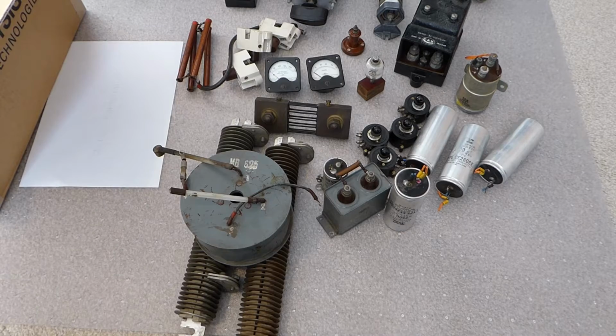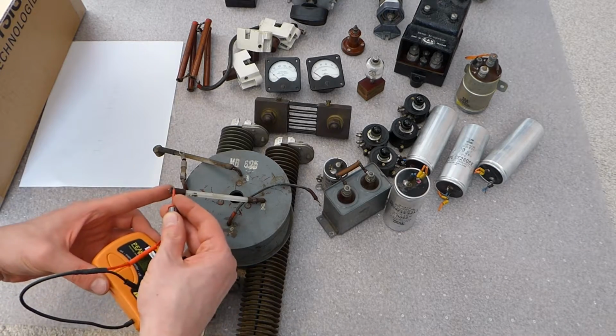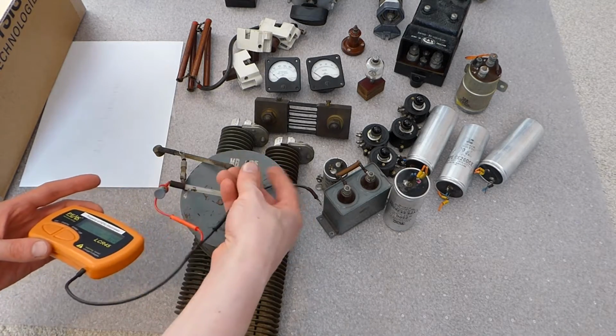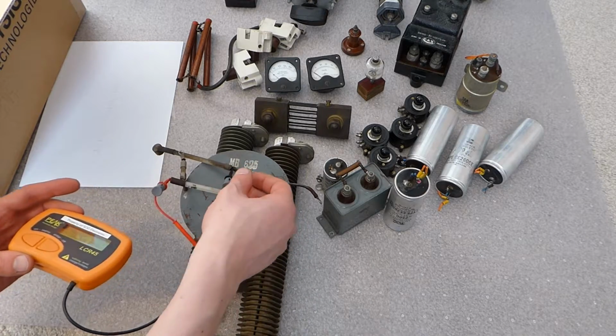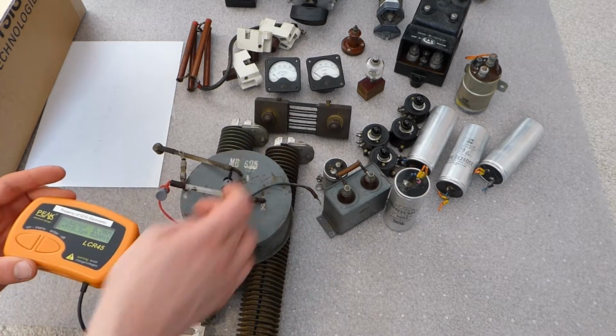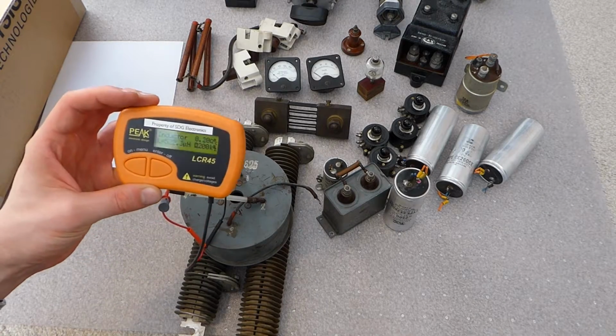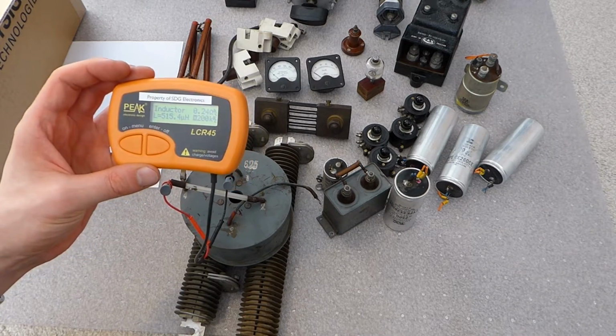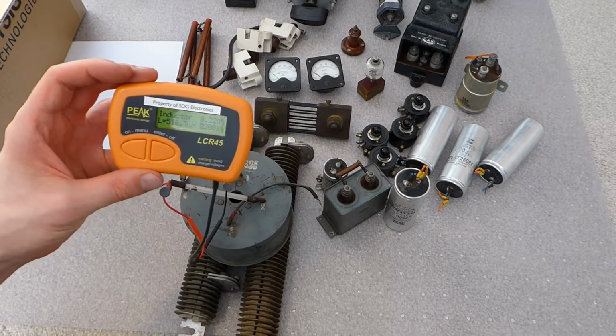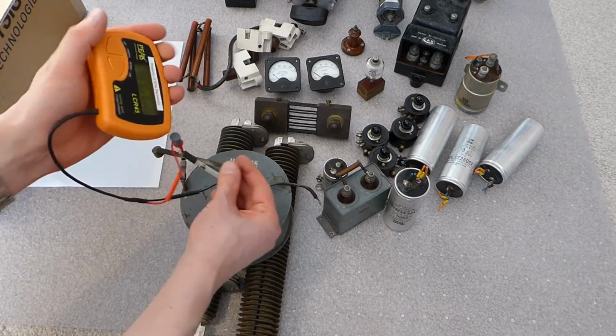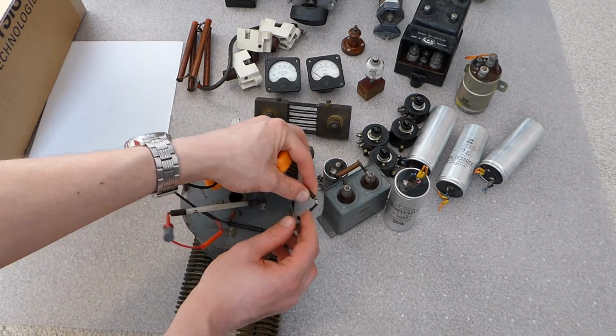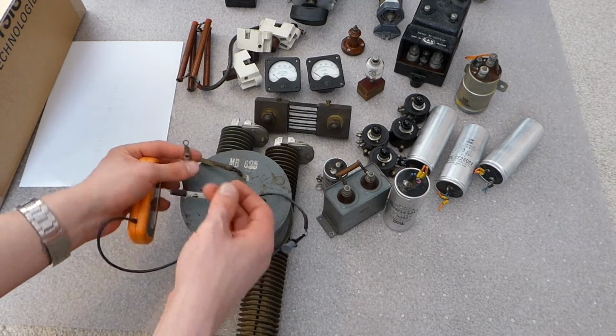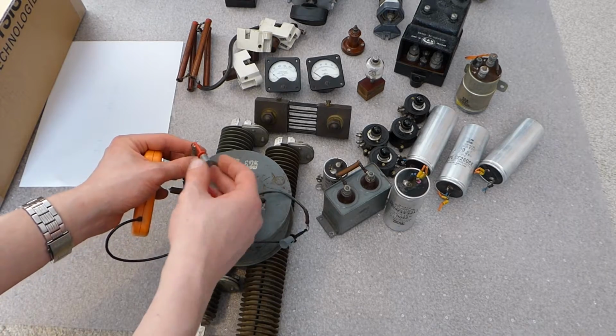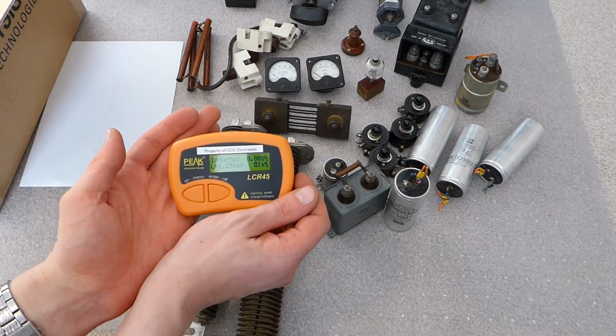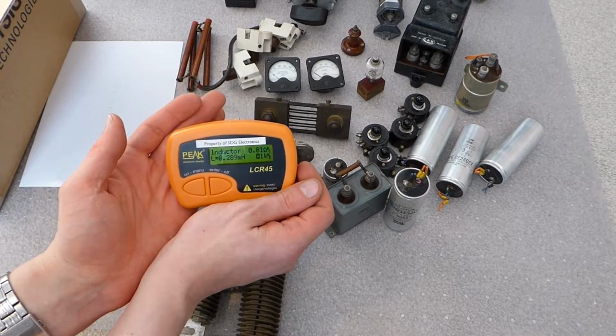First, let's measure the lower voltage side, which I believe is between here and there. Note that I don't have to actually get to the ends because the rubber insulation is all broken already. We're measuring about 520 or so microhenries. And the high voltage side is between here, and we get about 8.3-ish millihenry on the high voltage side.